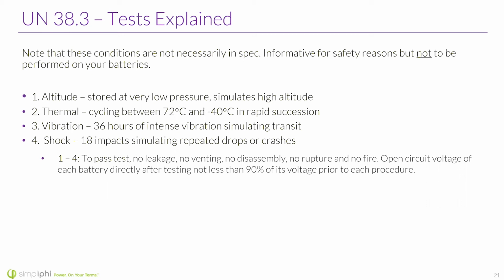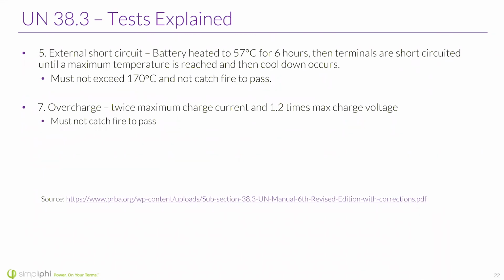Open circuit voltage of each battery directly after testing must be not less than 90% of its voltage prior to each procedure. So we do have this test and we have passed. And I guess there's two more that are called out. The external short circuit: battery heated to 57 degrees Celsius for 6 hours, then terminals are short circuited until a maximum temperature is reached and then cool down occurs. It must not exceed 170 degrees Celsius and must not catch fire for that test.